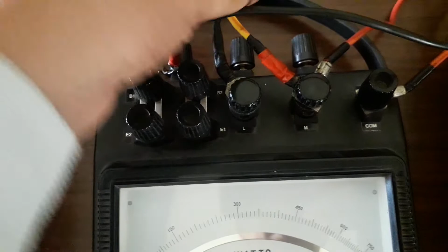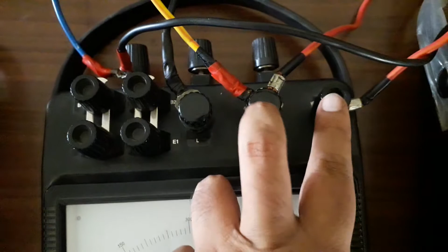From the ammeter terminal on the primary side, you can choose the 10 amperes range. From the 10 amperes terminal it is connected to terminal M, and you have to short this M and C, that is M and the common, to make the short circuit.